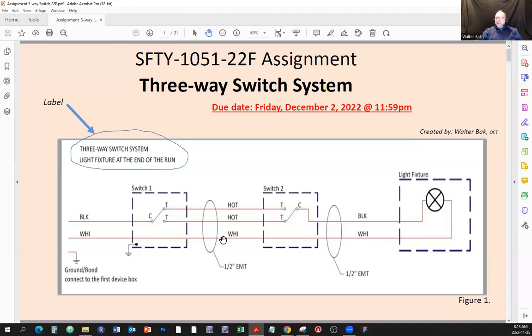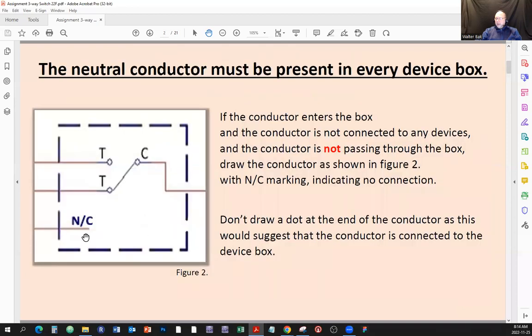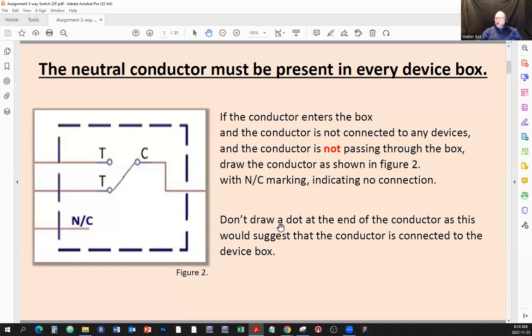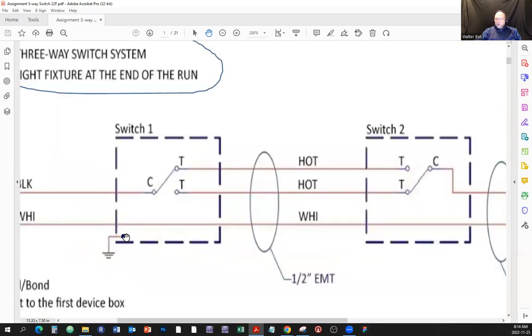You have to extend that white neutral and provide it there. If it's at the last box, just draw a line going into the box, and if it doesn't continue, draw it like this and put a 'not connected' indicator. If a conductor enters the box and is not connected to any devices and is not passing through the box, draw the conductor as shown in figure two with the NC marking. Don't draw a dot at the end because that would suggest the conductor is connected to the box, just like the ground is connected to the box.